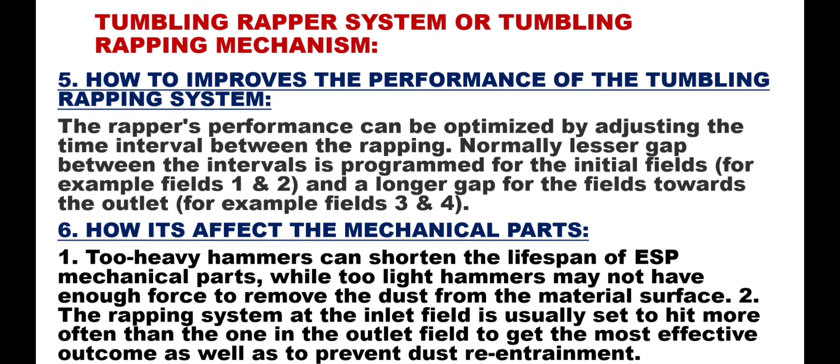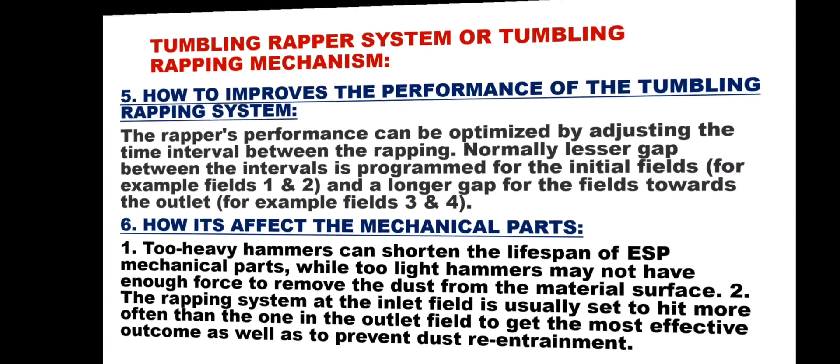Point 6 – How it affects the mechanical parts: Too-heavy hammers can shorten the lifespan of ESP mechanical parts, while too-light hammers may not have enough force to remove the dust from the material surface. The rapping system at the inlet field is usually set to hit more often than the one in the outlet field, to get the most effective outcome as well as to prevent dust re-entrainment.